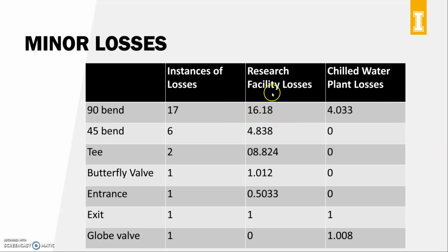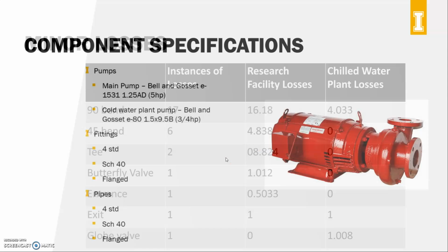And our largest head loss by far is just going to be our 90-degree bends. That's not really surprising. And then we also have a pretty good loss coming from our T as well. And we have a little bit coming from our 45s. And these are in feet. This is 16 feet and 4 feet, or approximately 5 feet, 8 feet, etc.